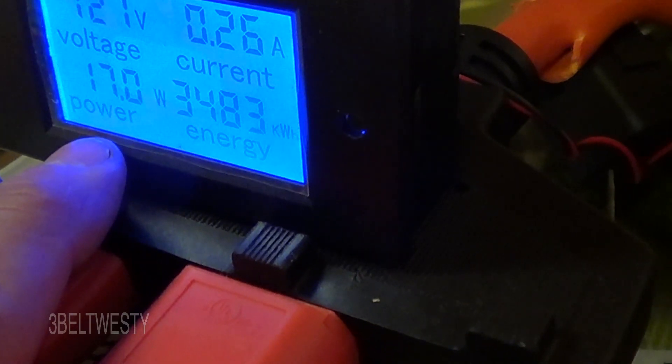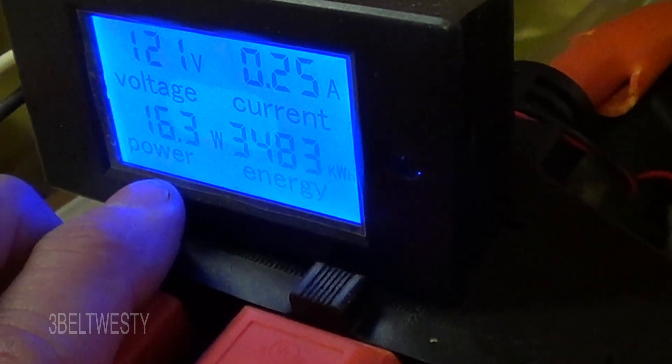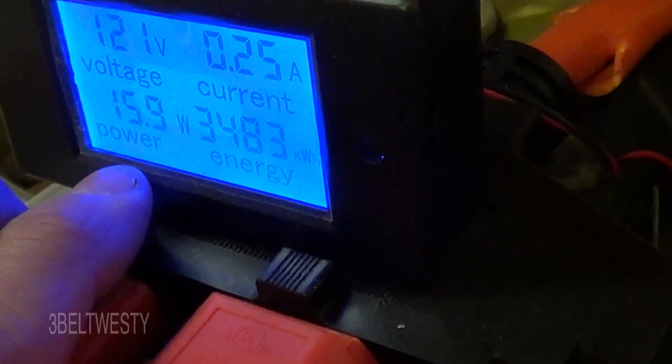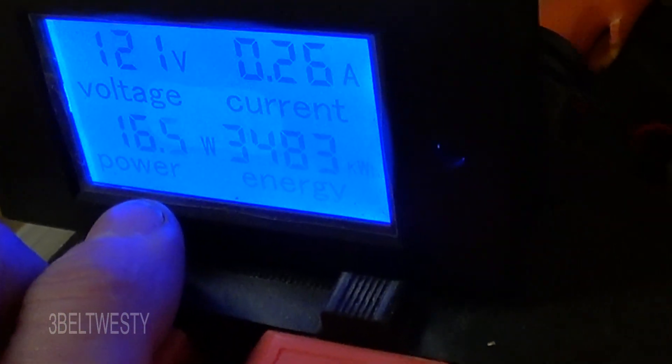But when it's cold I've just noticed that there's a crankcase heater that kicks in. And I noticed this last year, and I just didn't really think about it, but I've noticed that once it's cold outside there must be an internal crankcase heater that turns on.